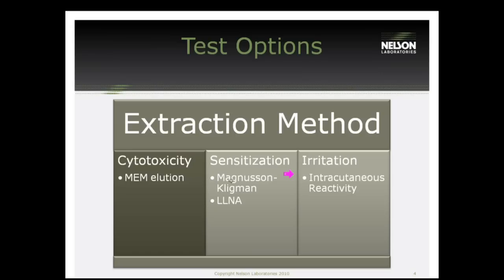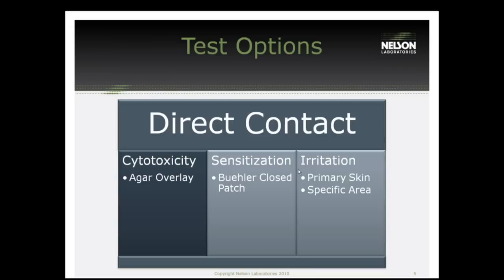Here are the extraction versions of these tests. We're looking at the MEM elution for the cytotoxicity test, the maximization or the LLNA for sensitization, and intracutaneous reactivity for irritation. For the direct contact versions, if you have a skin contact device, this is what you want: the agar overlay for the cytotox, the Buehler closed patch method, and a primary skin or specific irritation contact area. These give you an idea of testing you can choose depending on whether you want direct or indirect.